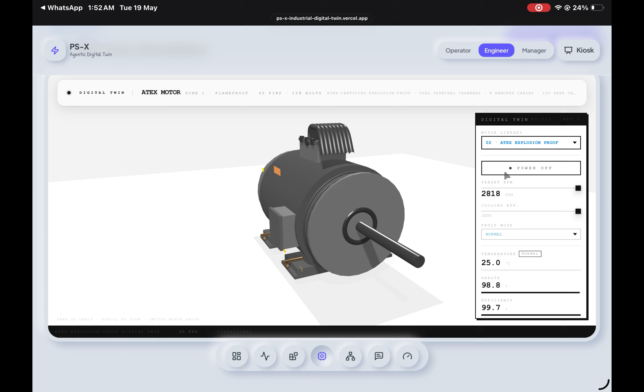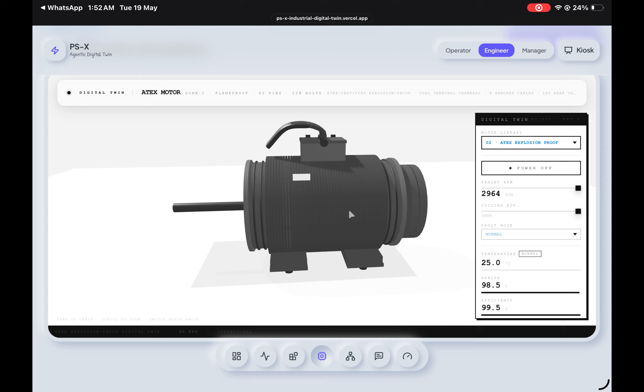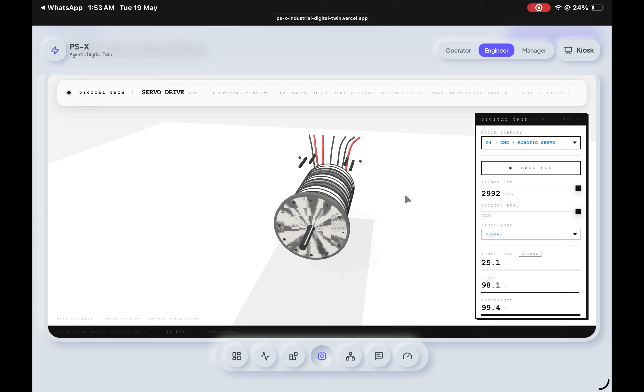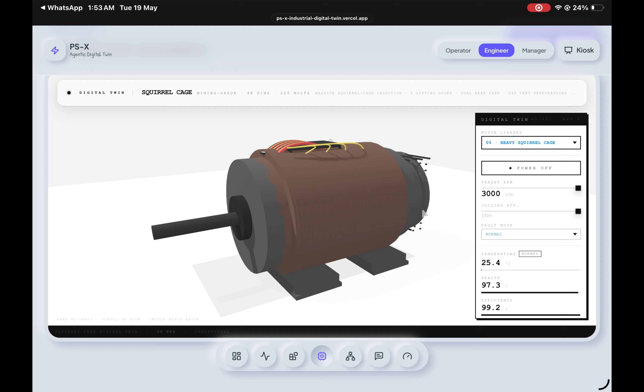We also simulate how changes in motor load affect parameters such as current consumption, heat generation, rotational stability, and operational efficiency. For example, when cooling efficiency decreases, thermal rise inside the motor increases, which affects winding insulation, bearing stress, rotor balance, and long-term machine reliability.